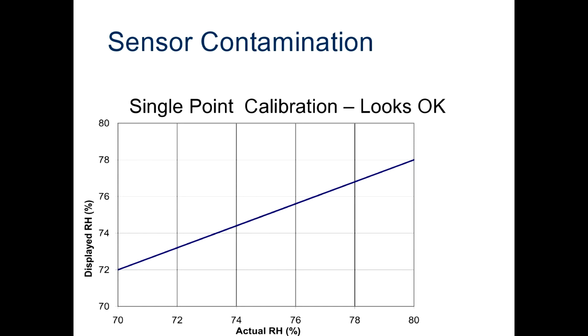Let's look at a real-world example of what can happen when we have surface contamination. This is a case where a measuring device underwent a single-point calibration at around 75% RH. Now, as we can see from its results, it actually looks pretty good. It's pretty close to being at 75% in every regard. At or near 75%, which is the actual RH shown on the bottom of the graph, we can see that the corresponding measured value is pretty close.